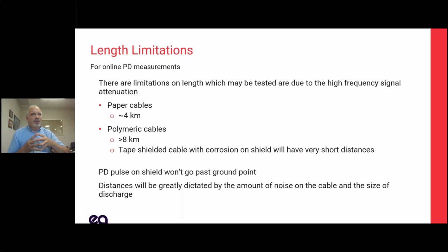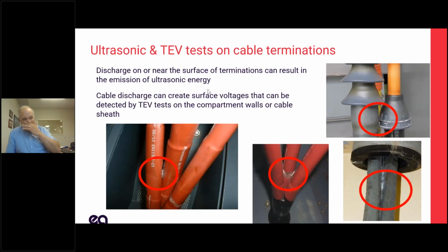If you've got access to both ends, you can test the same cable from both ends. That's a really helpful thing to do. You can also, in your terminations, test for TEV and ultrasonic, which is other parts of what our instruments do. These are cable failures. The discharge in the air is creating a lot of ultrasonic energy. So if you're doing a cable test, also do a TEV test and an ultrasonic. That's going to give you a really good indication of the health of your cable.